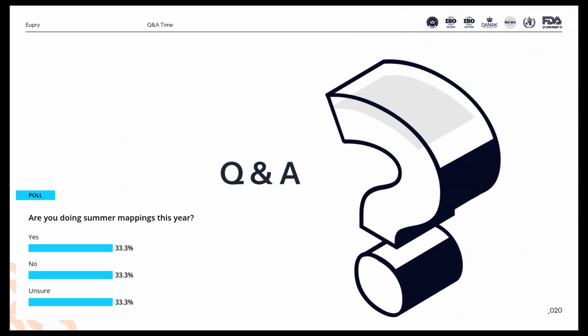Really good question again, and we've gotten this several times. I would say I've seen two strategies being employed. One is where you have a summer hotspot and a winter hotspot, and you switch the position between those two, and one where you use two sensors for the hotspot, basically to cover both the winter and the summer scenario.